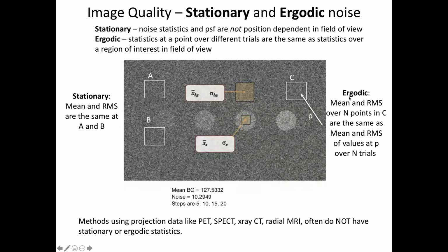In that, ergodic is a really neat concept. Say I have 1 pixel here, right? And I look at the value of that pixel, and I take 1,000 images. And then I plot the signal intensity I measure at that pixel over those 1,000 images. So I'm not moving my pixel around anywhere. I'm looking at a single pixel. I plot its value as I move through those 1,000 images, and I get a random number, or I get a mean and a random fluctuation around the mean. When I measure that random fluctuation around the mean, that's a sigma value, right? That's that RMS value. If I get the same sigma value when, say, I did 1,000 images and I have 1,000 pixels inside this box, if I look at the root mean square deviation of the 1,000 pixels in the box and it's equal to the root mean square deviation of the 1,000 images, that process is ergodic. That's what that means, right?